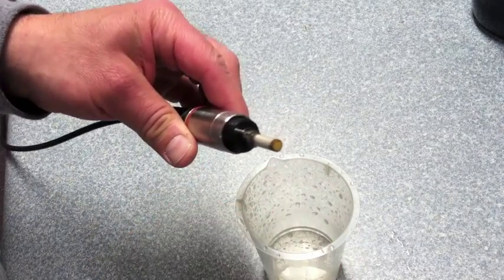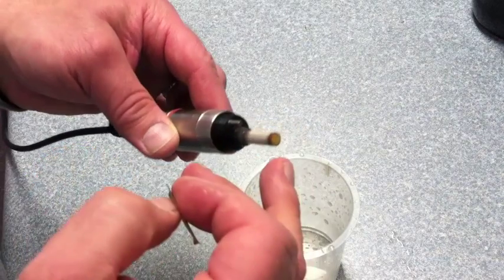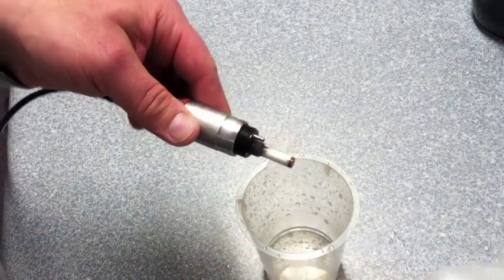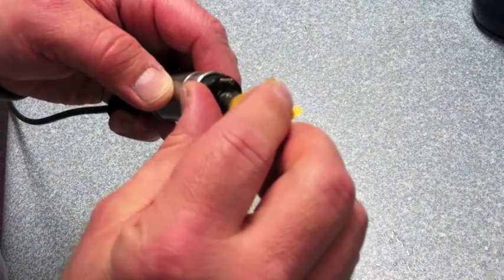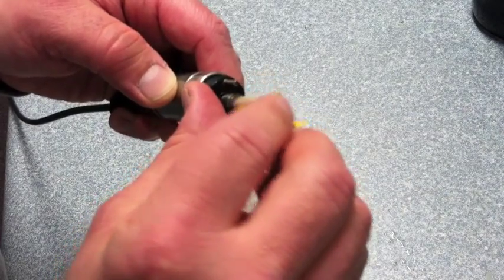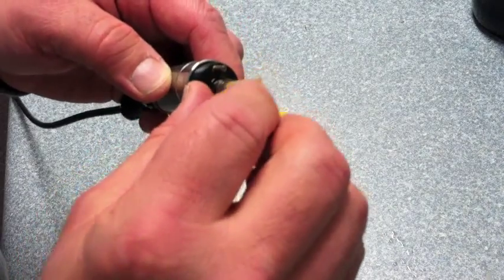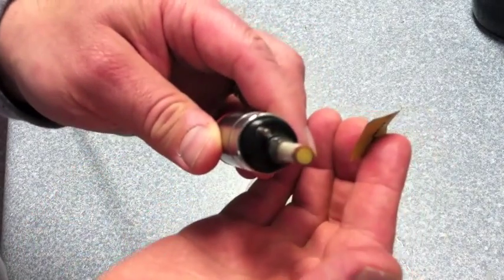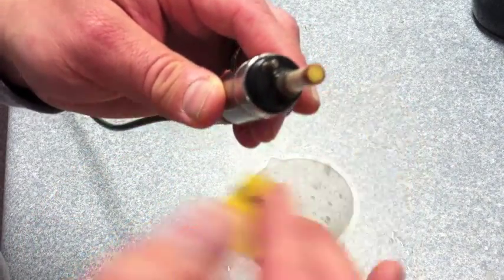So then getting back to the mechanical cleaning on the gold, you want to make sure that you clean off any of the residue as the silver has transferred to the gold. And you want the gold just to be a bright brass color. And you just want to have it have a matte finish. So just carefully look at your probe and just make sure that there is no silver that's left on it.